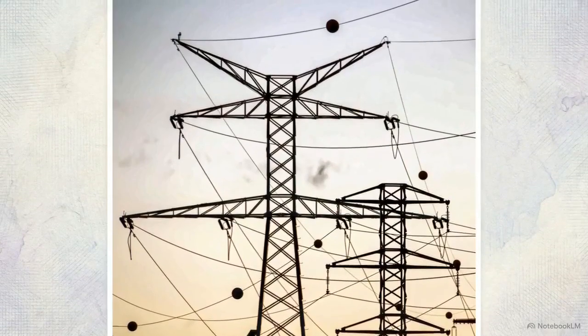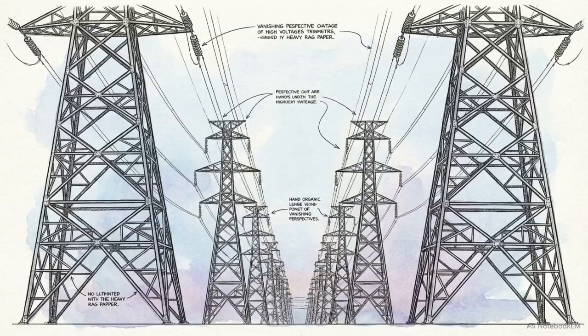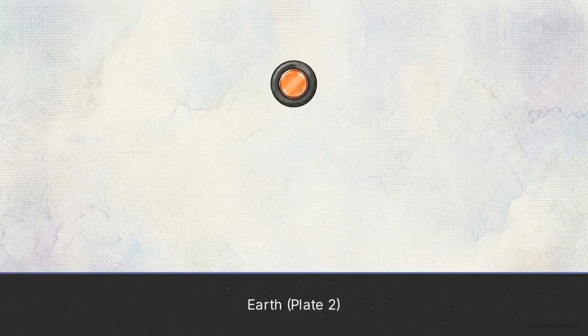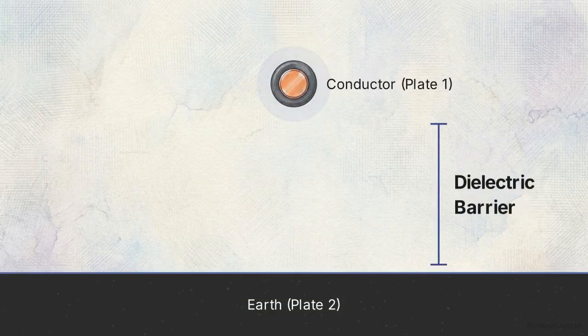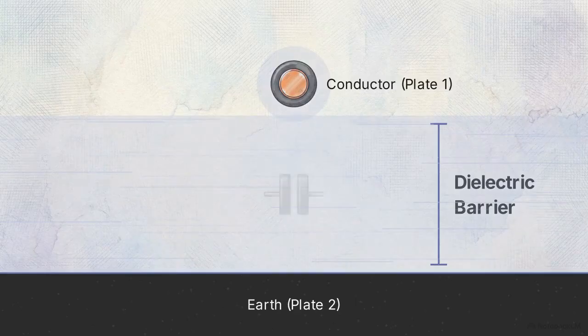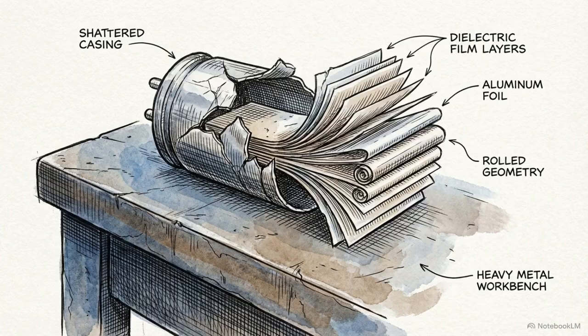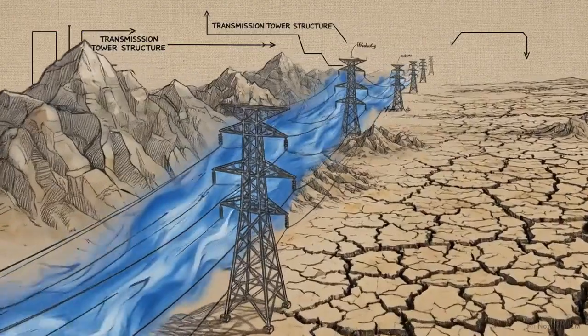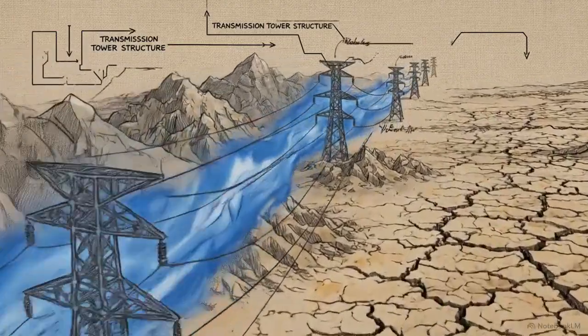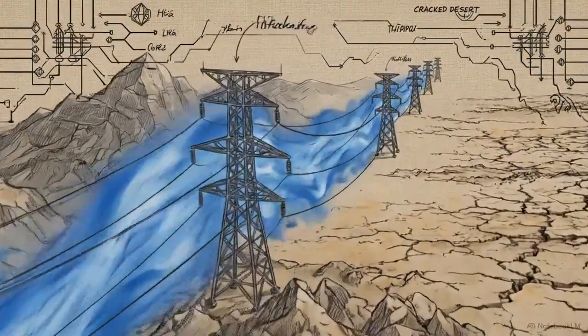The wires are spaced far apart in the open air, but overhead lines compensate for that low density with immense length. When you string a live, high-voltage conductor high above the ground, the air gap between the wire and the earth acts as a dielectric barrier, the exact insulating material found inside standard electrical components. By extending that wire across a state or a continent, the accumulation of distance turns the entire physical structure into a massive, geographically distributed capacitor.